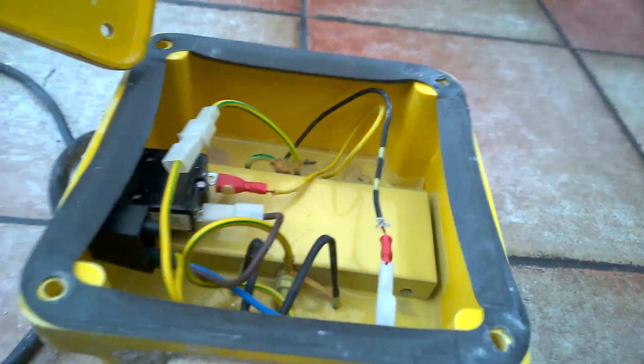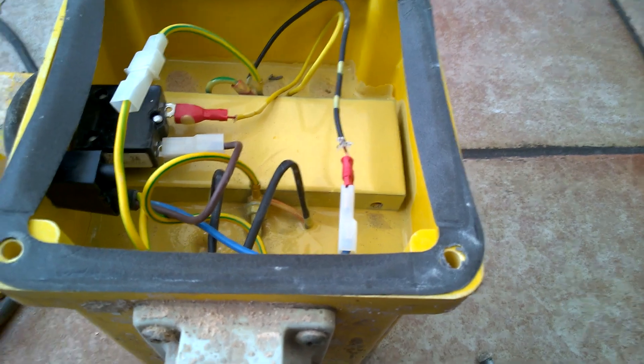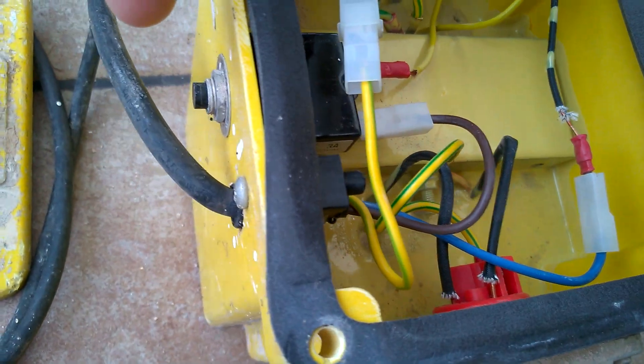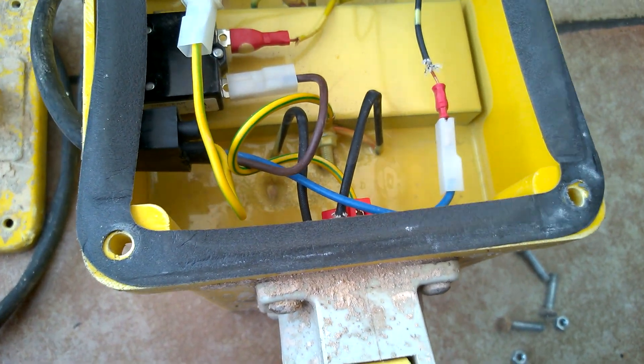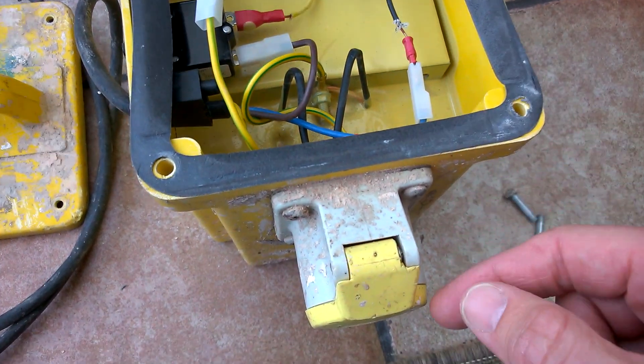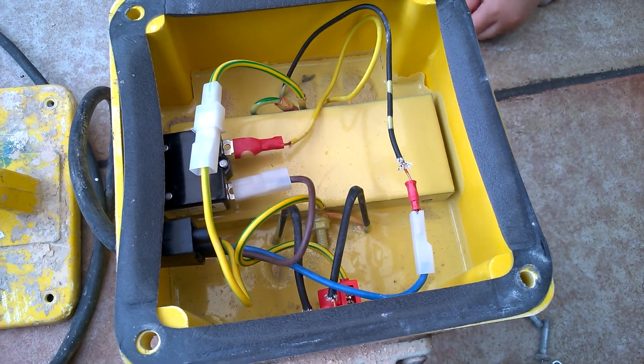It's open. Don't touch anything, because you don't know if it's still got any charge. This is what's inside — not a huge amount actually. There's the reset switch on the side, and we've got plenty of earth cables. Inside it's all potted, so underneath here will be a huge transformer taking 240 and dropping it down to 110 volts.